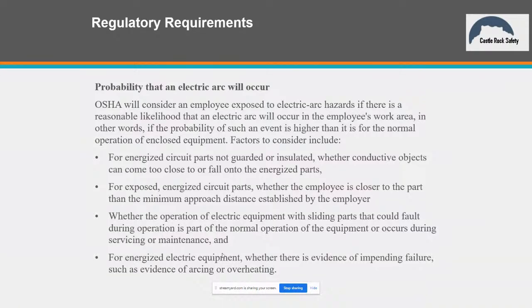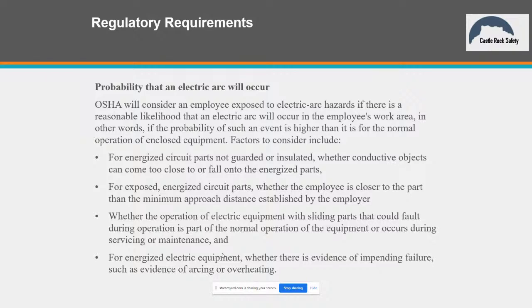It's a little less, it's not in table form, but it basically just says that if you've got an employee, he may be exposed to an arc in his work area if the probability is higher than it is for normal operation, and they give you these factors to look at. If I've got energized parts that are not guarded, and there could be some type of conductive object that could fall into it, that would obviously increase the risk of an arc flash. If I've got energized parts and the employee is closer to the part than the minimum approach distance, then I've got to have arc flash clothing on.